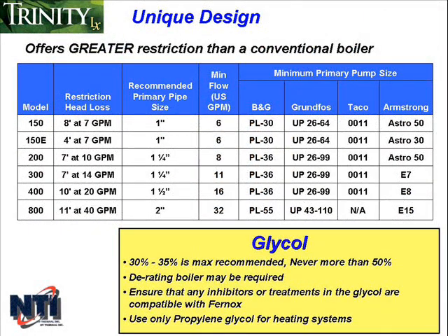The Trinity Lx boiler uses a low mass heat exchanger that requires a minimum rate of forced water circulation anytime the burner is operating. In order to make sure the minimum flow rate is attained at all times, the boiler needs to be installed in a primary-secondary plumbing configuration using closely spaced T's to decouple the boiler loop or primary loop from the system loop or secondary loops. You'll see examples of the primary-secondary loop configurations in Part 2 of this segment on boiler plumbing.